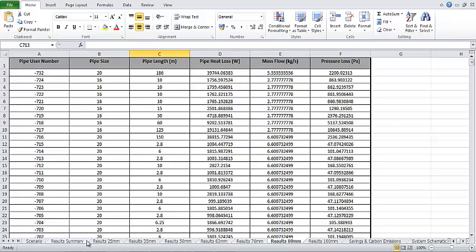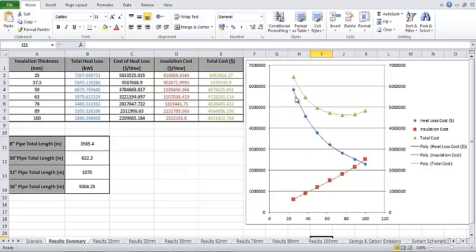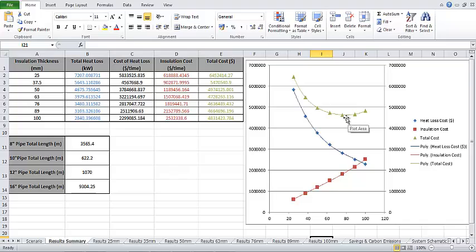If we select Result Summary, we can see a detailed table of results and an associated graph plot of insulation cost, heat loss cost and total cost. If we position the cursor over this region here, we can see that an insulation thickness of 76mm represents the most cost effective solution.